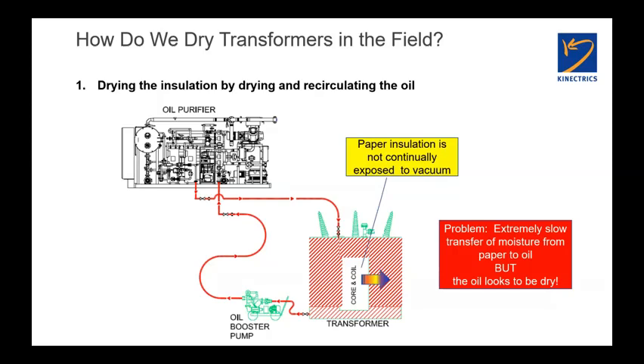You connect up your oil processor, you recirculate hot oil through the transformer. The oil purifier is going to heat up the oil to about 65 C. We don't want to go much higher than that because we'll start to damage the oil. And over time, we will pull the moisture out of the oil. But because of those longer time constants, we're not really attacking the moisture that's in the paper. The problem is, how are we going to measure the moisture content? Often there's a meter on the oil processor that will say there's so many parts per million of water in the oil, or maybe we're going to do some other indirect test here.